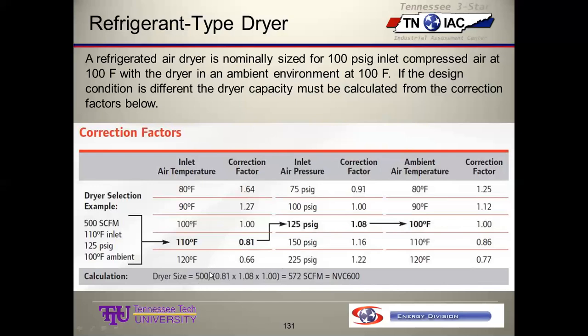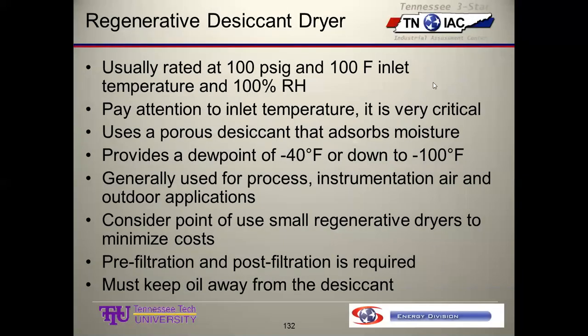Okay, so what you do is you take this nominal, or this 500 SCFM out of the compressor, and you divide it by the product of all 3 of those correction factors. And when we do that, the math produces 572 SCFM, so we always round up. We would buy one size larger dryer for this in anticipation of these more aggressive inlet conditions. So pretty straightforward, but it's kind of interesting how that works out. Okay, so that's the end of our refrigerated dryer discussion. And we'll move on to the desiccant here.